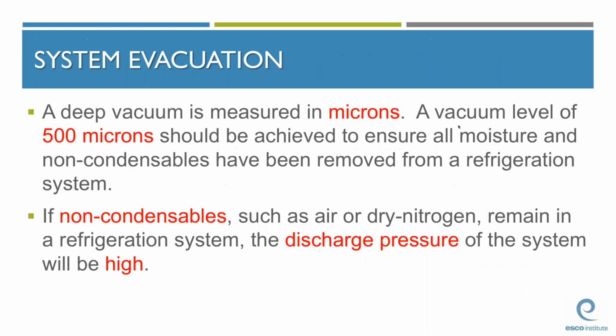Just a couple of quick words about system evacuation. It's important that your students know how to measure deep vacuums and know how to use the instrumentation, namely a micron gauge, to do so. So that magic number, that vacuum level of 500 microns, needs to be achieved to ensure that all the moisture and non-condensables have been removed from the system. Common non-condensables are air and nitrogen. If non-condensables remain in the system when it's charged and put into operation, the discharge pressure will be higher than desired and the system will not function as intended.